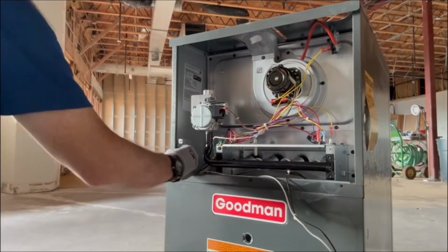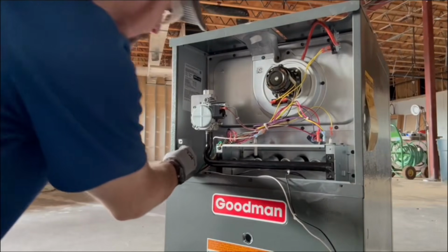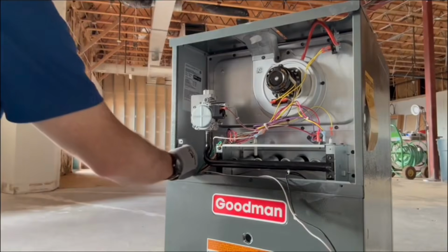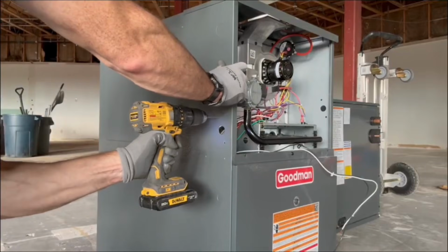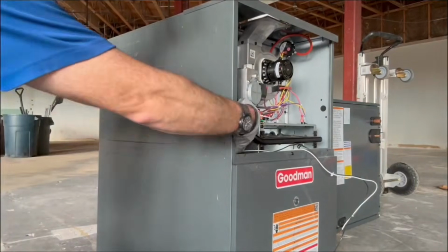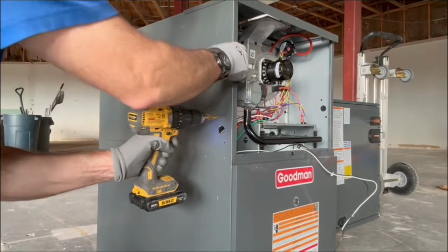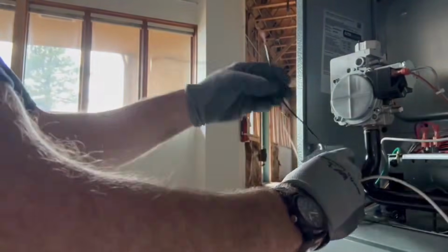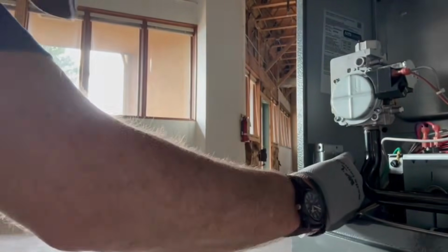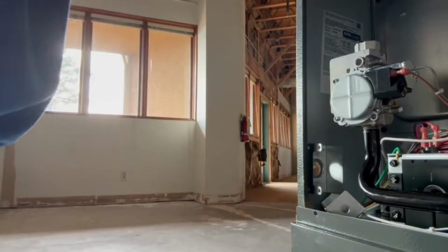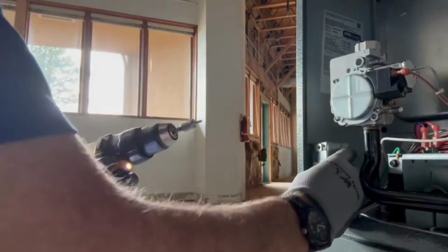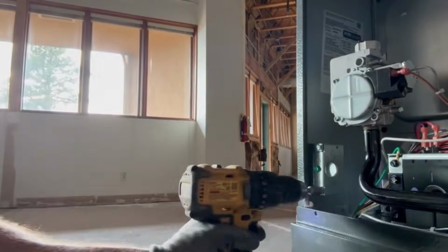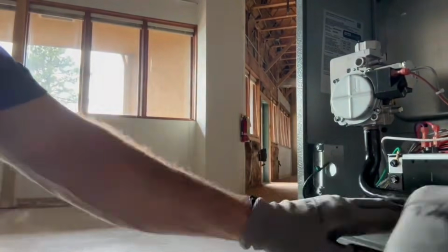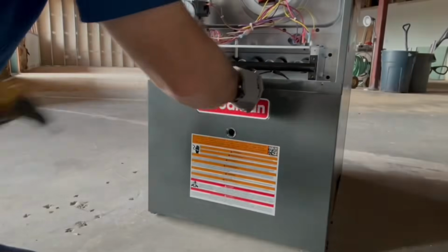And so this is where our 120 volt single phase power will come in to the furnace. Drill my mounting holes for the screws. Got my J-box. Clean up my holes. Black hot wire, white neutral wire. Don't forget your green ground wire. I'm trying to get everything prepped as much as I can before I bring it into the occupied suite and up on the roof. I'm doing this in a vacant suite, so that was nice.